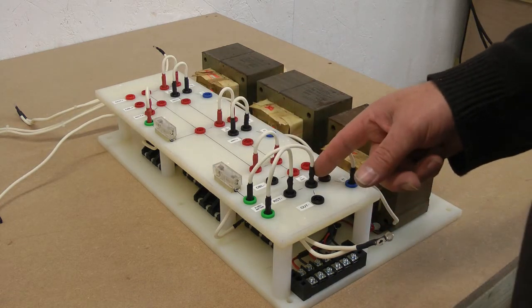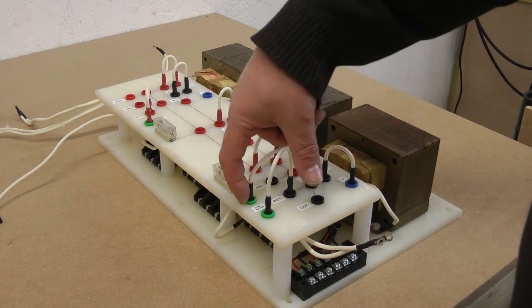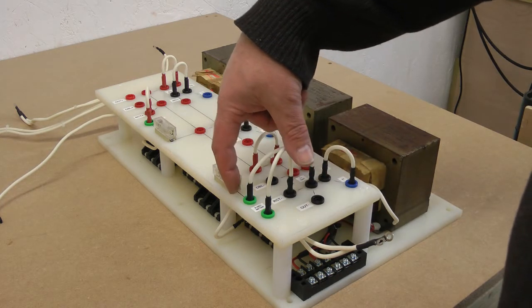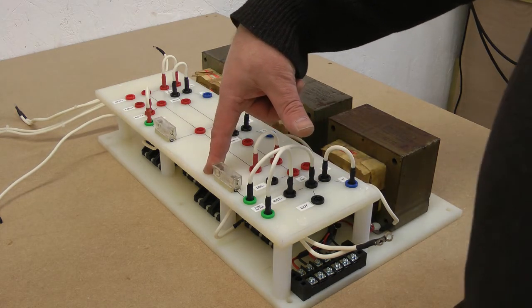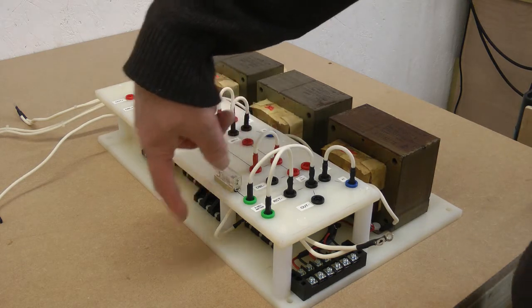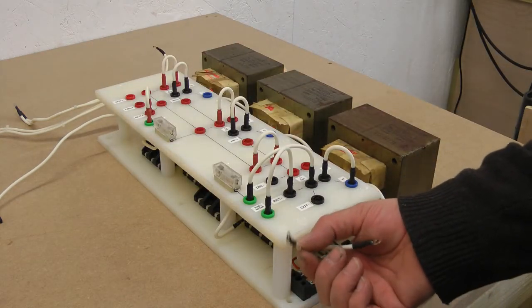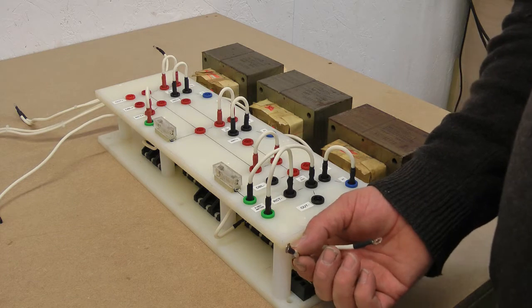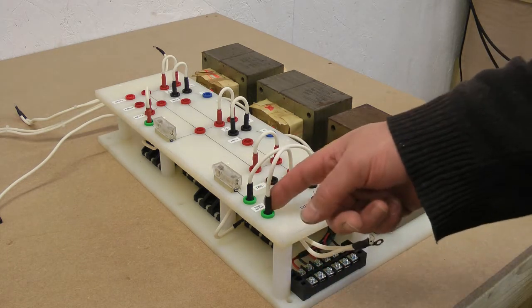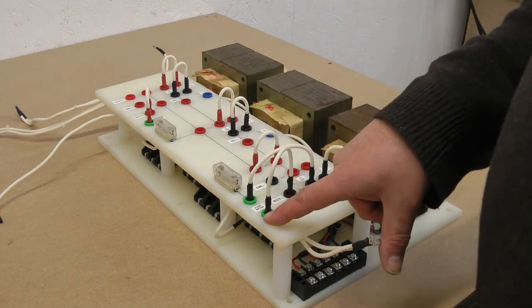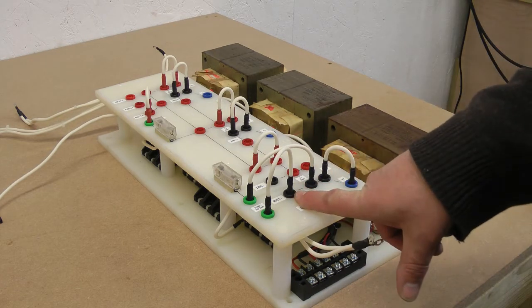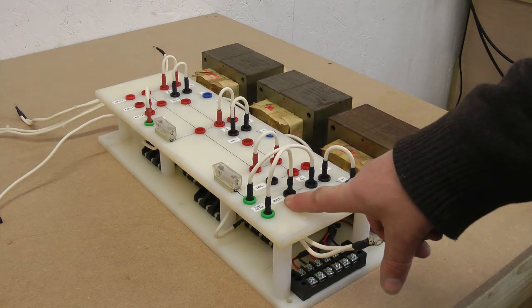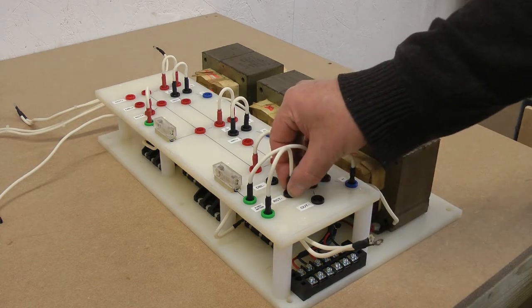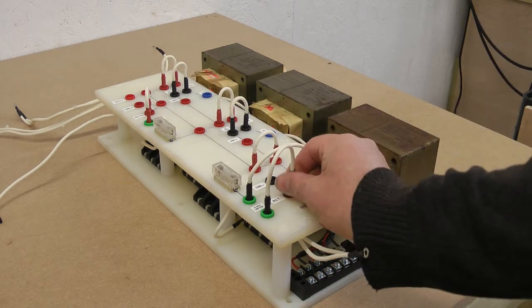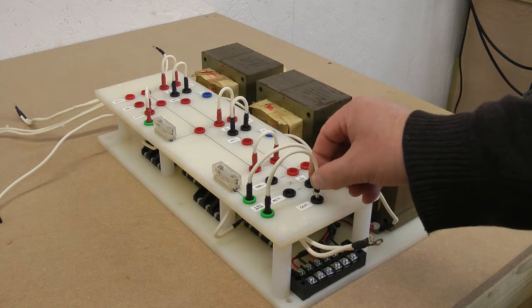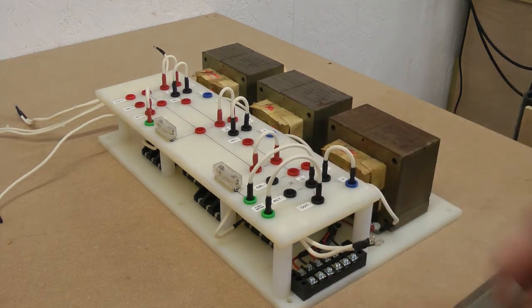So in effect, the negative terminal comes down here, is connected into this green terminal, goes through the fuse, and then the output of that fuse goes down to one side of the current meter. The other side of the current meter is the return, from here back to, and here we've got it plugged into the negative end of the rectifier. I might have that, for example, plugged into the negative end of the raw output.